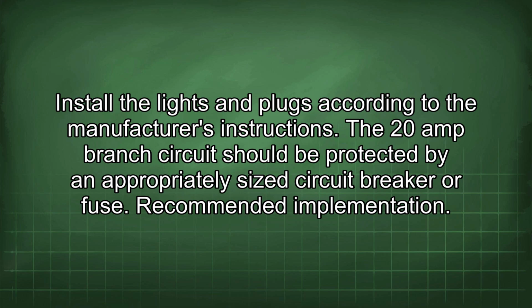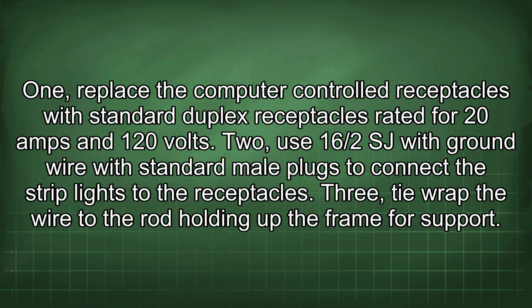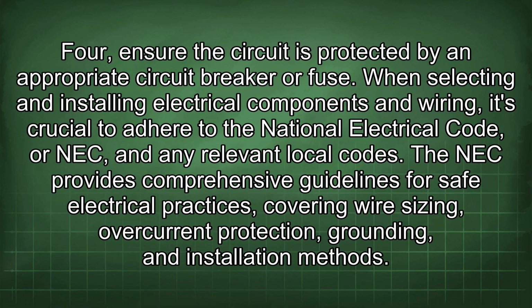Recommended implementation. 1. Replace the computer-controlled receptacles with standard duplex receptacles rated for 20 amps and 120 volts. 2. Use 16/2SJ with ground wire with standard male plugs to connect the strip lights to the receptacles. 3. Tie-wrap the wire to the rod holding up the frame for support. 4. Ensure the circuit is protected by an appropriate circuit breaker or fuse.